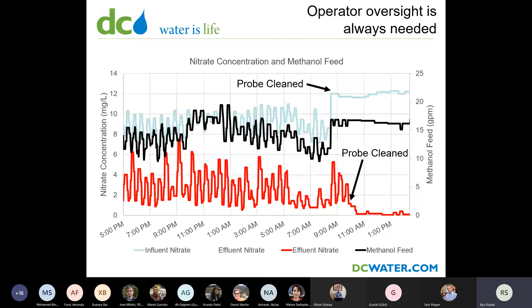Just one practical challenge that we have: if you're looking at this trend, I think it's very apparent that the probe is fouled or there's some kind of problem, because it doesn't make sense. But for our operators, this is just one of thousands of different process variables they need to stay on top of. So just because this one went bad, it's difficult to catch it right away. And there's a little dichotomy: the more robust your control system is and the less problematic it is, the less attention we as operators typically pay to it. So when there is a problem, sometimes it's hard to jump on it right away.